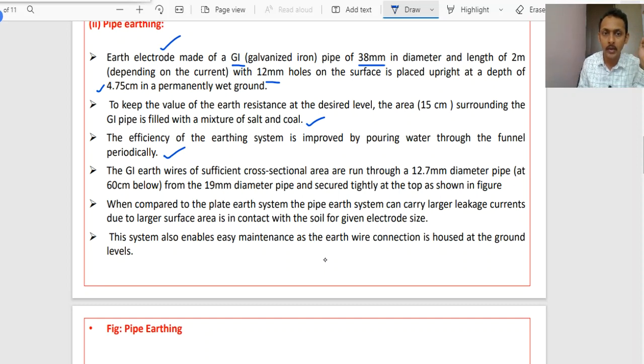You have to pour some water in order to maintain that pipe earthing system. Now the GI earth wires of sufficient cross-sectional area of 12.7 mm diameter pipe from the 19 mm diameter pipe are secured tightly at the top, right? When compared to the plate earth system, the pipe earth system can carry a large amount of leakage currents due to the large surface area in contact with the soil for the same given electrode size.